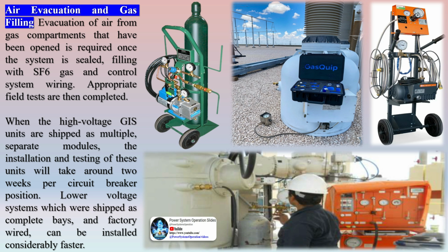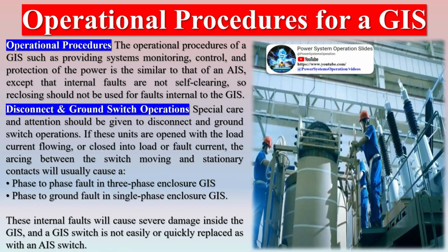Air evacuation and gas filling. Evacuation of air from gas compartments that have been opened is required once the system is sealed, filling with SF6 gas and control system wiring. Appropriate field tests are then completed. When the high-voltage GIS units are shipped as multiple, separate modules, the installation and testing of these units will take around 2 weeks per circuit breaker position. Lower voltage systems which were shipped as complete bays, and factory wired, can be installed considerably faster.